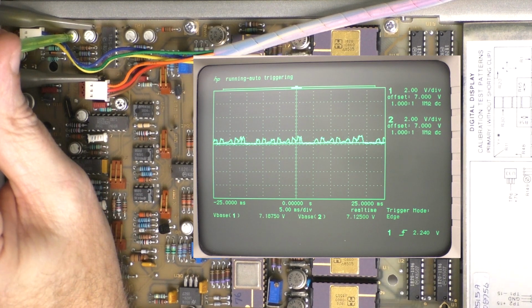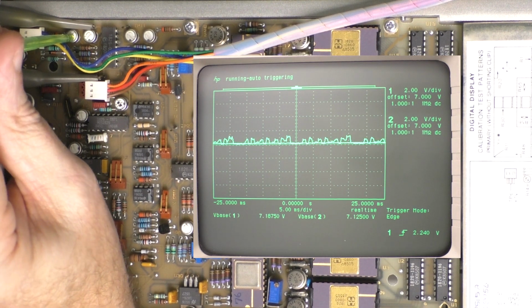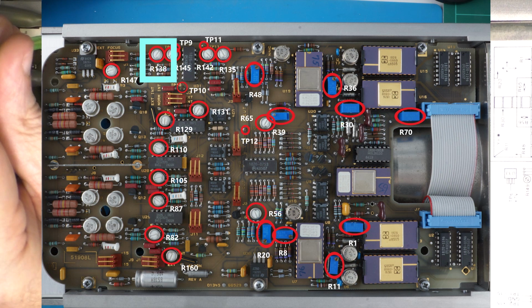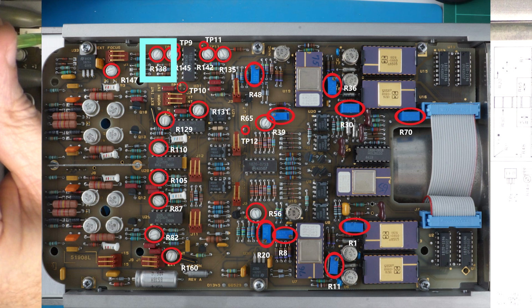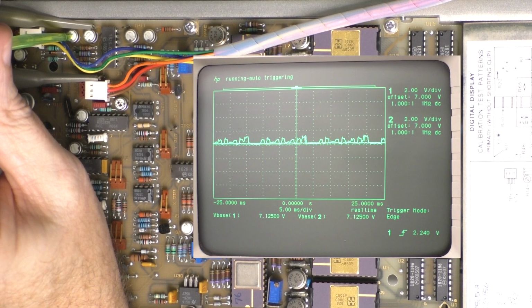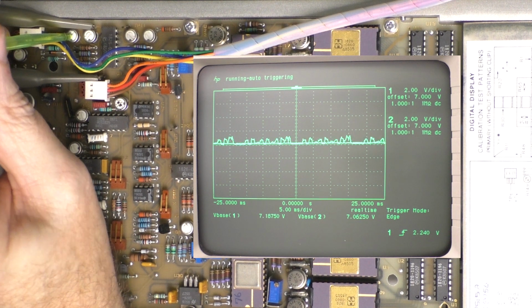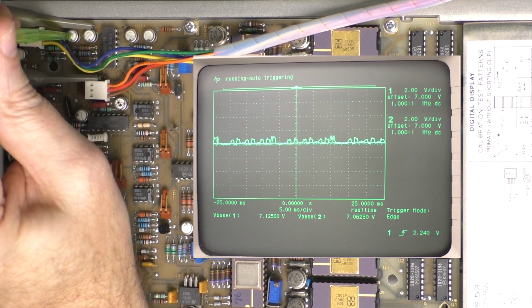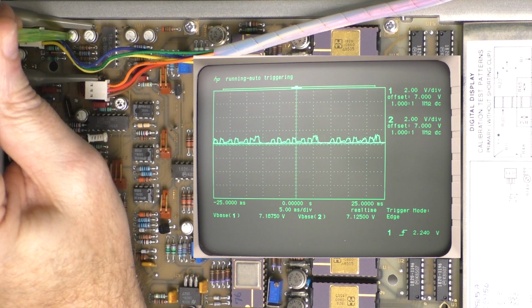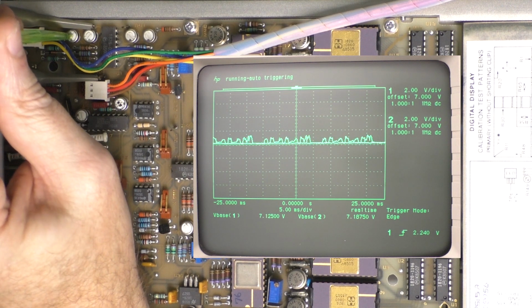Set the scope to 2 volts per division, 5 milliseconds per division. Locate R138 on the A1 board. This adjusts the Y focus offset. We need to adjust R138 so that the base voltage matches the base voltage at test point 9, 7.1875 volts.